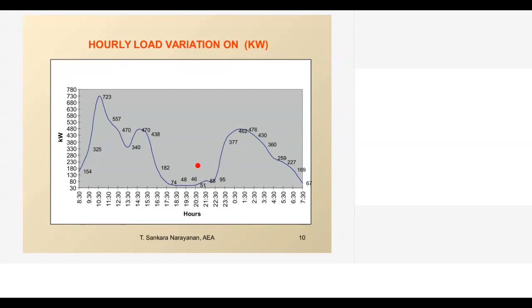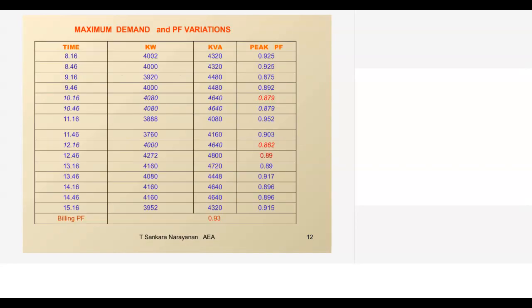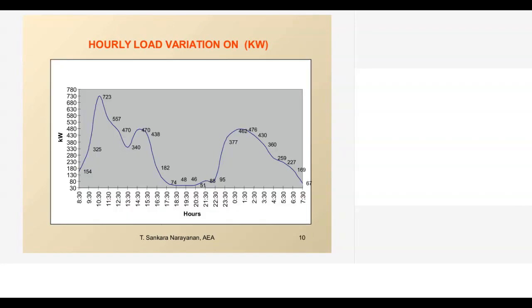When I am able to reduce my production level between evening peak hours, I can still have control over my peak demand. This type of load curve generation was earlier practiced by some of the old industries; railways used to maintain the substation-wise load curve. Utility companies used to maintain the load curve. But today we are slowly not generating this. So whenever an audit is done, if we are able to generate this for a normal production day, this will also tell how the demand utilization can be optimized. So one, based on the production requirement and the demand, we can see how the demand monitoring or demand optimization has to be done.